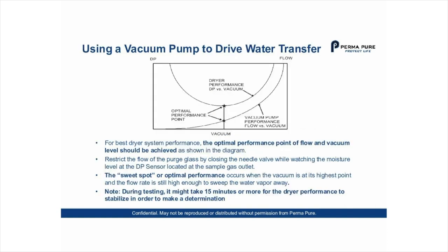The next phase of this presentation concentrates on how to use a vacuum pump to drive the pressure differential across the membrane in order to generate purge gas and effective moisture transfer. This is a little complicated, and we really suggest that customers looking to use a dryer with a vacuum pump understand that for every vacuum pump and dryer combination, there is an optimum performance point that needs to be found for the system.